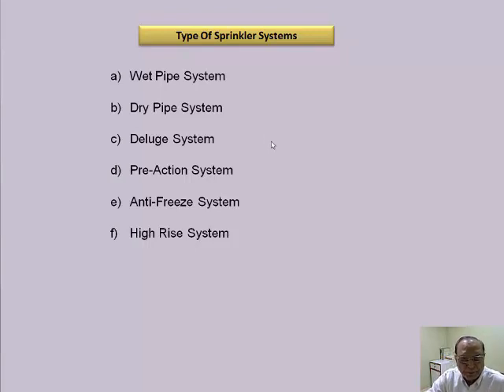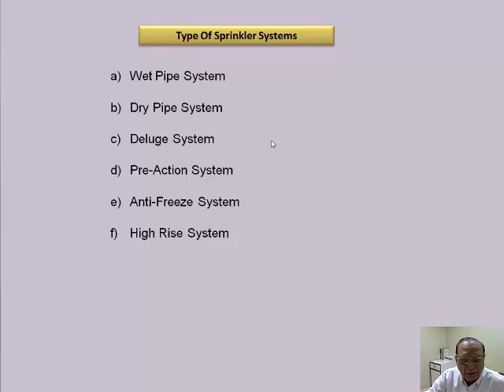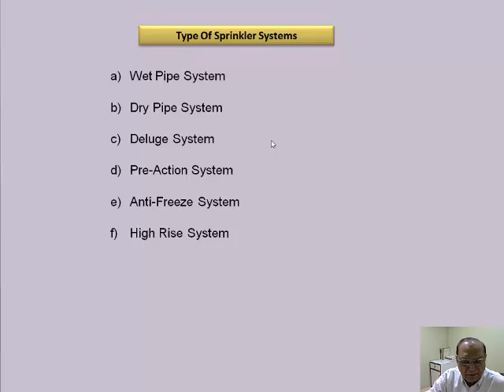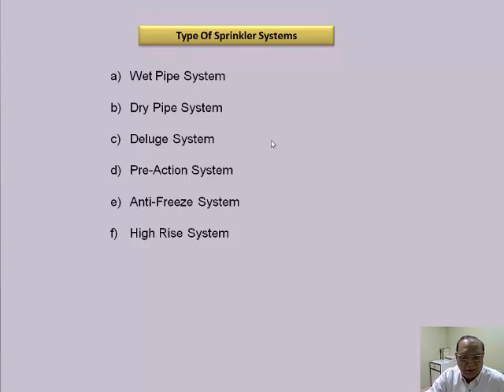Deluge system uses open sprinklers or open nozzles which discharge water. After opening of the deluge valve, being open nozzles, there is no water beforehand — the water remains pressurized up to the deluge valve. The deluge valve is operated either by a smoke detector signal, heat detector signal, or it can be operated manually.